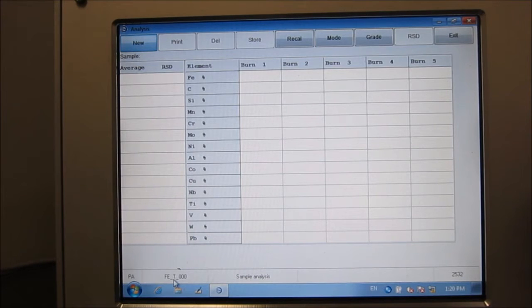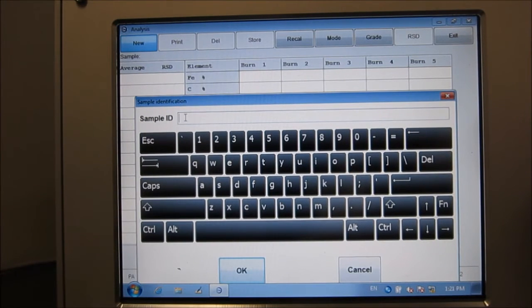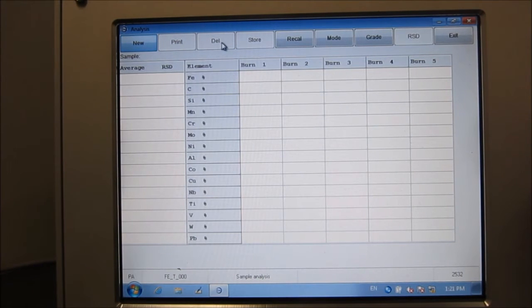Here we are now running on the universal subprogram, and it is the sample analysis mode, and here is the number of times that this machine has sparked. So you have a counter here to tell you how many times you have sparked and whether it is time for you to clean your electrode or your probe. Now over here you see the button new. If you click on that, you will see a keyboard appearing so that you can key in the name of the sample or the sample ID. But since we are not doing any measurement right now, I will just recall a stored analysis. Cancel this. Over here you will see recal, which I'll go to later.